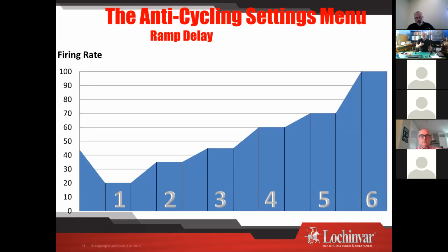We didn't create all this excess wasted energy. We extended out our cycles. And what we're doing is we're targeting much better to get to our water temperatures. This is what we're doing. I bet if you go down and watch a lot of boilers that are set up with that 140, 180 outdoor reset curve, you're seeing that things are satisfying long before they get to their targeted water temperatures. So it's just one more piece of the puzzle that you can put together to tie in this, hey, how am I going to do a good job making my boiler as efficient as possible?